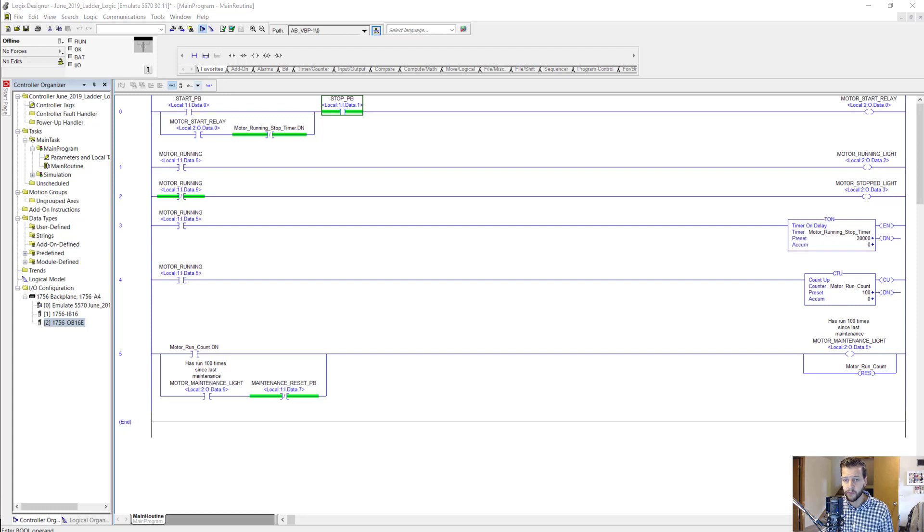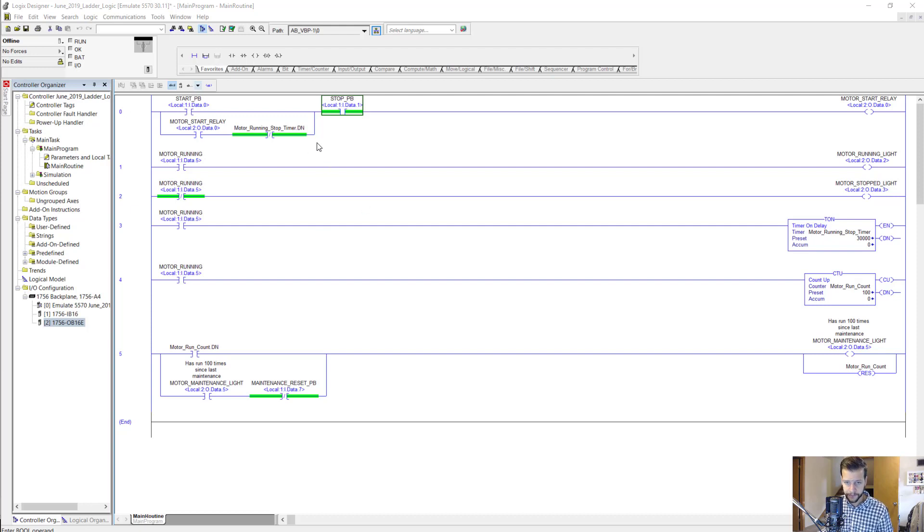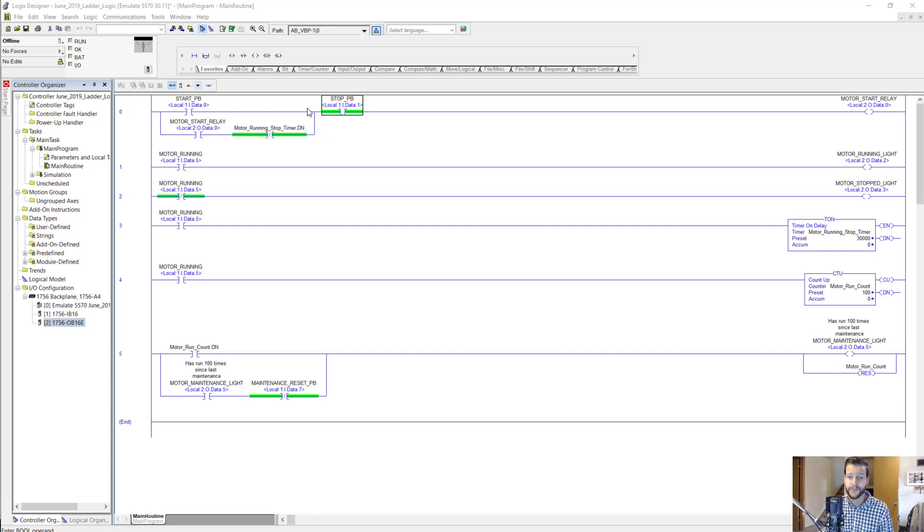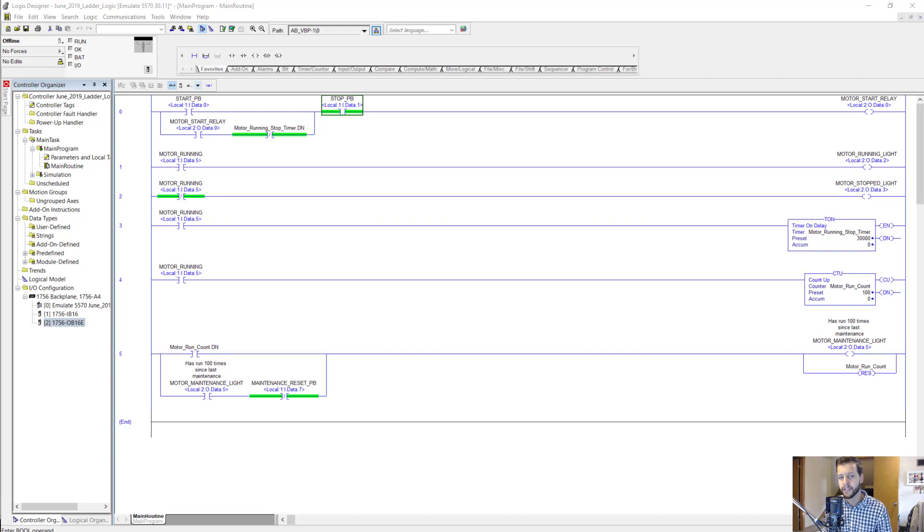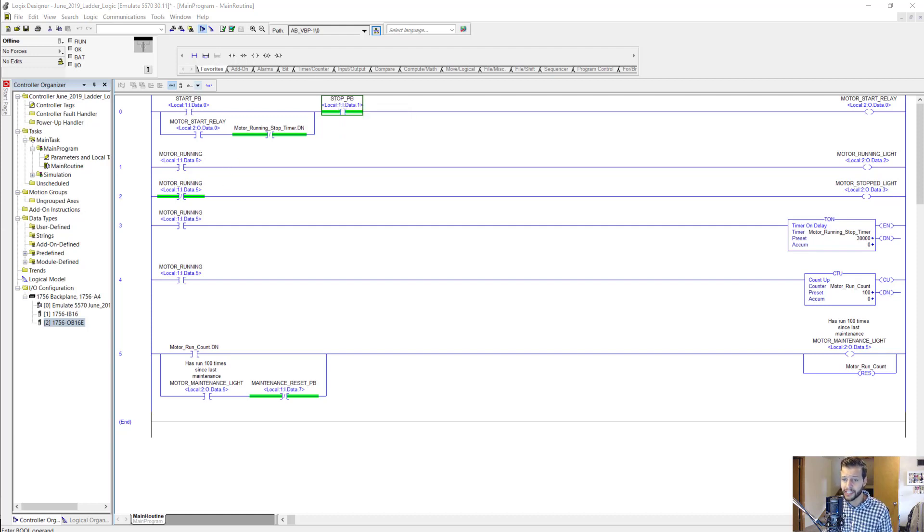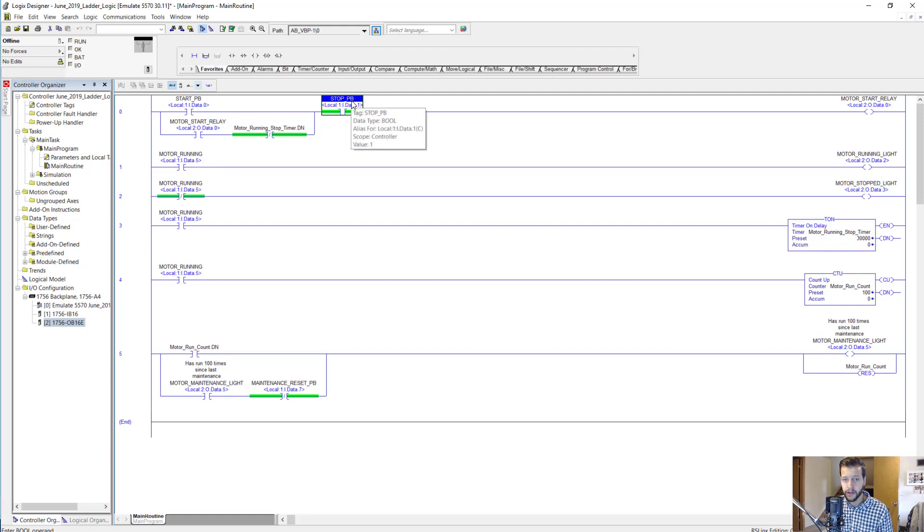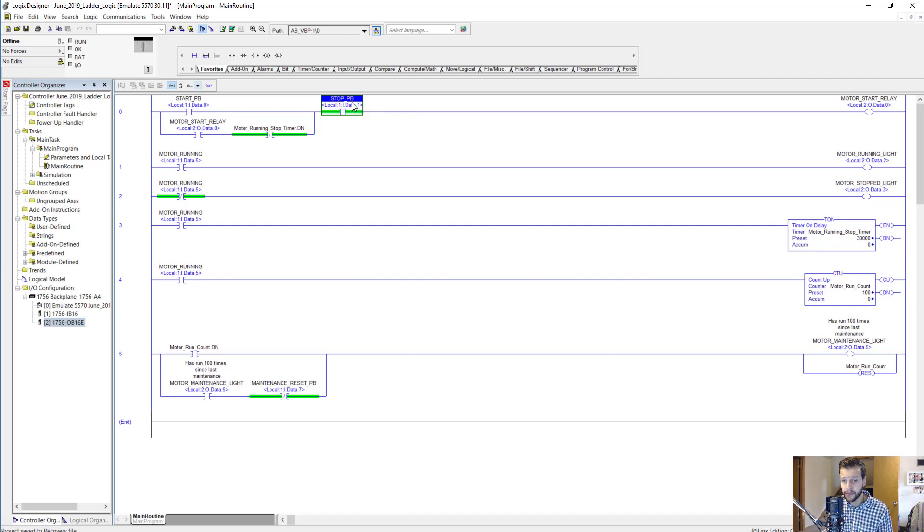Here's why. One of the concepts that we have developed in industrial controls over the years is the idea of making a circuit fail-safe. In other words, designing your controls in such a way that if a control circuit or device or battery source fails, the equipment it controls will shut down rather than keep running without a way to shut down, because that's not a good situation. What we want for our stop button control is that if the wires or the push button fails for some reason, or a wire becomes loose and loses connection, we do want this logic to shut off the motor. We don't want it to keep running.